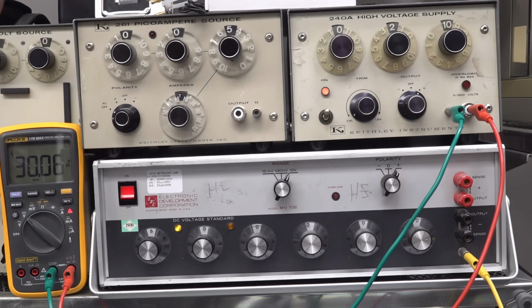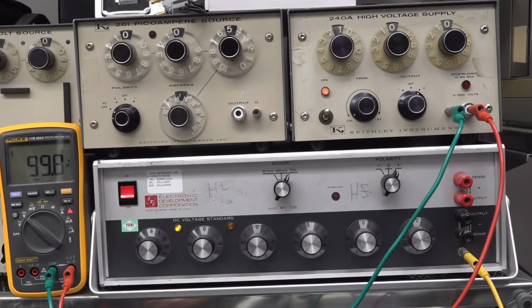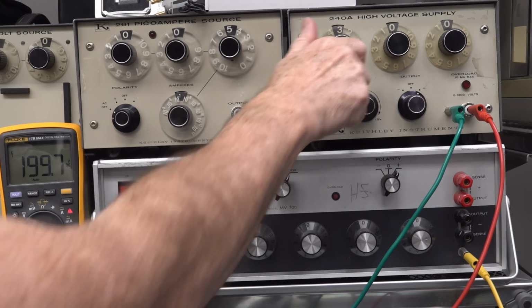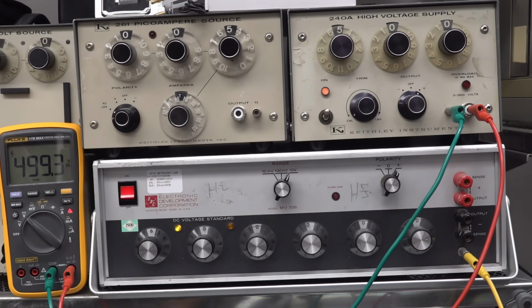30 volts. Yeah, high voltage warning indicator at 30 volts. It's a bit low, isn't it? Anyway, let's wind the wick up. This is not an accuracy test because it's not a particularly high accuracy unit. We just want to test the overrange. 500 volts, 600 volts, no worries. 700, 800 volts. Will it go to 1,000?